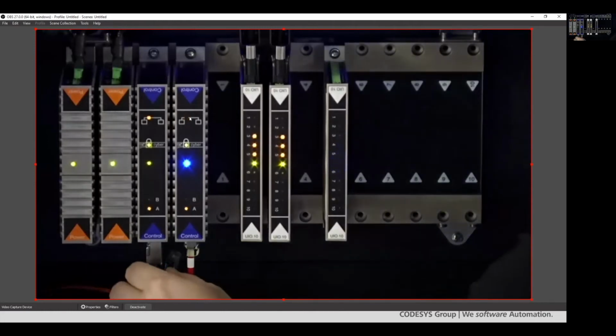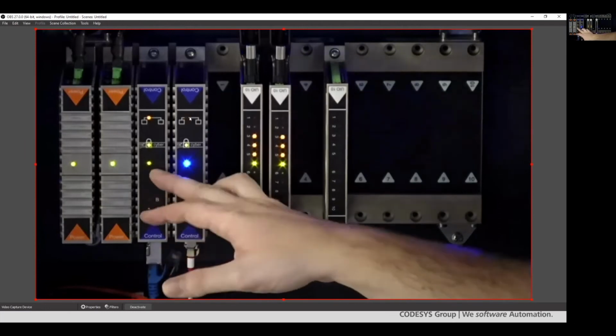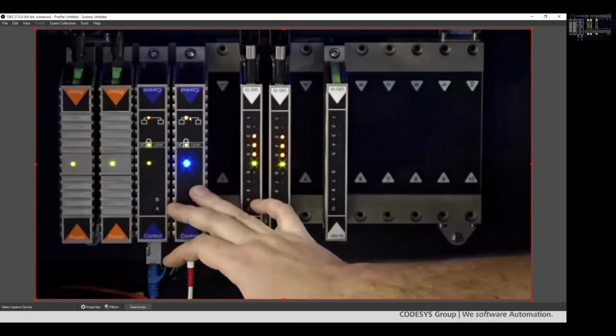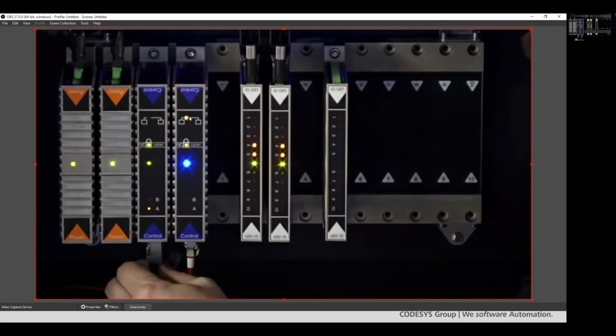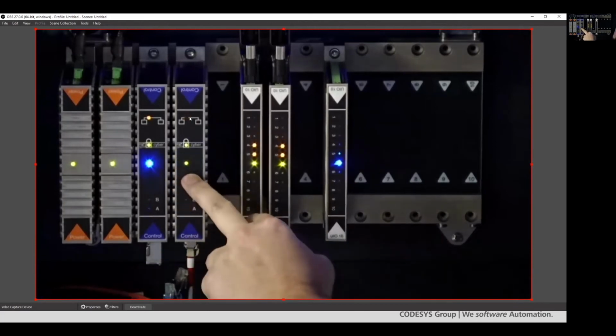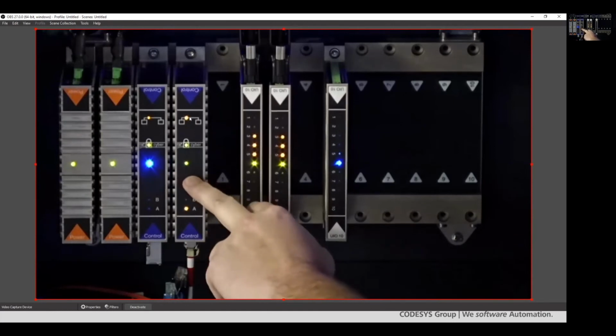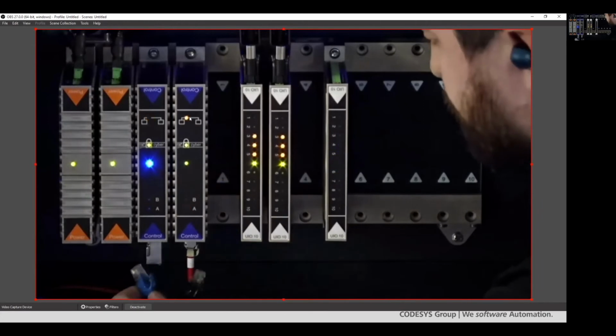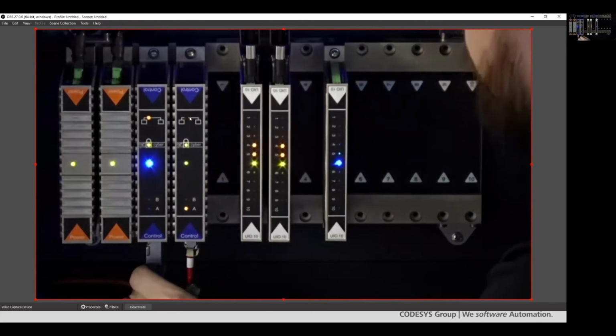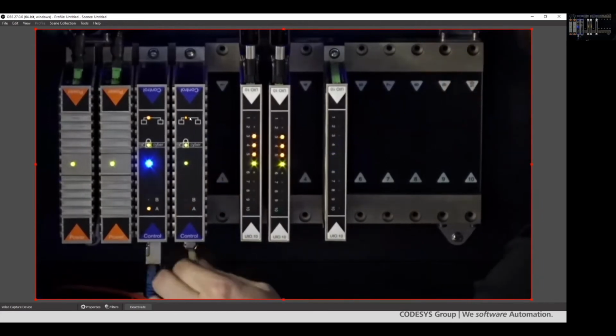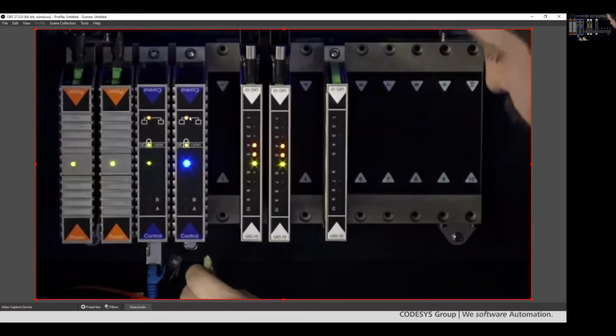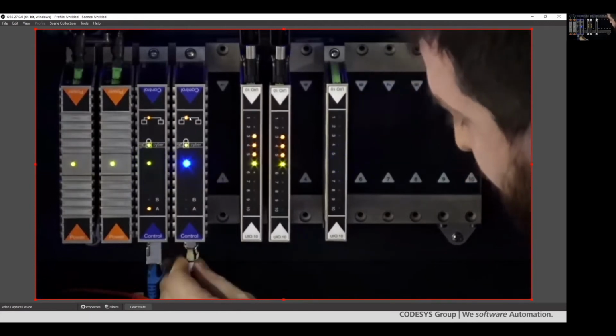With the program, you'll actually see this is running in the active state, while this is running in the passive state. So as we do a loss of communication, you see the control instantly switches over to the new passive, the old passive controller becomes the new active controller. So that data is able to switch back and forth with full communication between the two.